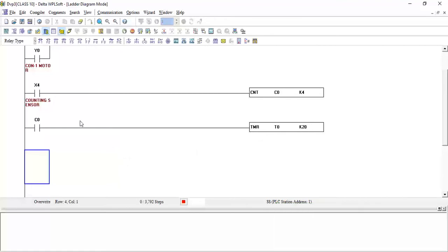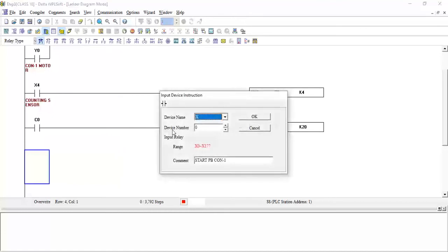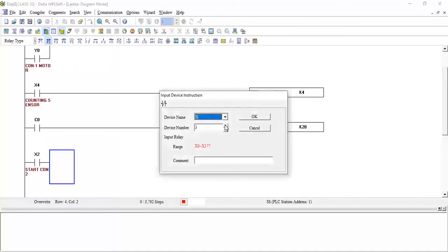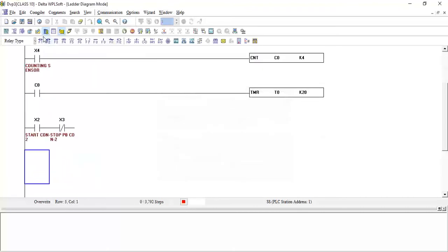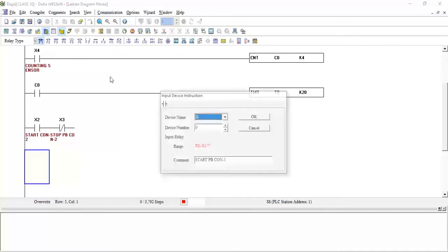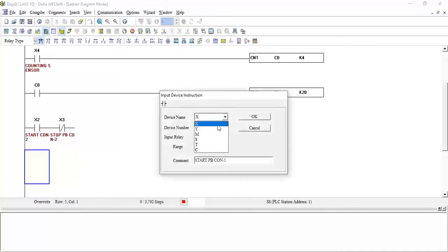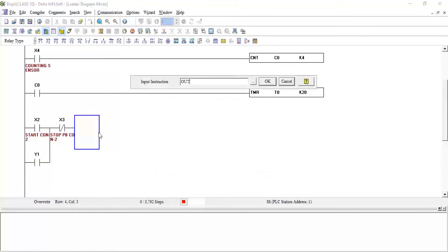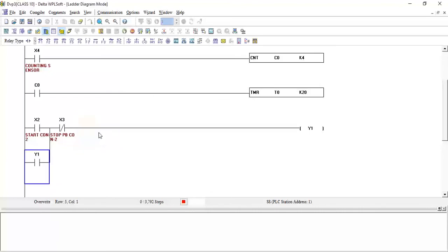First we take manual push button start conveyor 2, because we need the manual start stop push button for conveyor 2 also. I will take start conveyor 2 push button at X2. For the stop I will take NC and it will be X3, stop push button conveyor 2, click OK. In parallel I will add latching for Y1, OK, and I will connect it here. Let it output Y1.